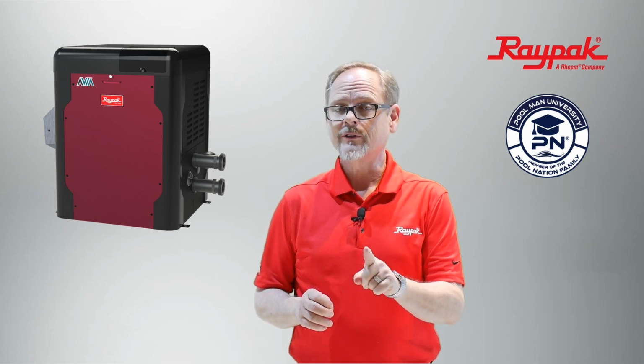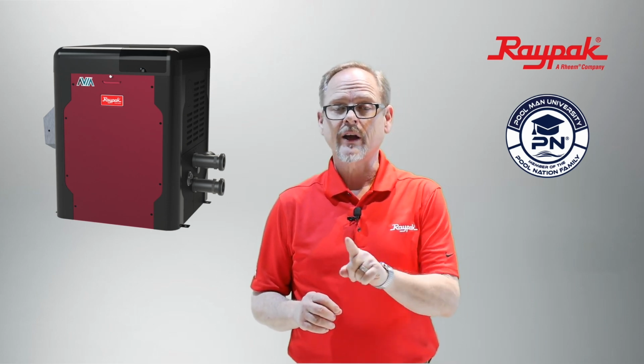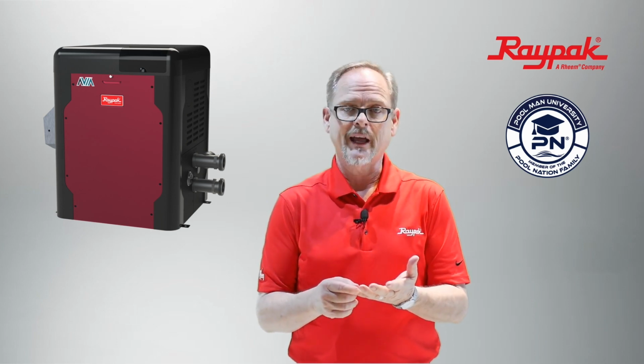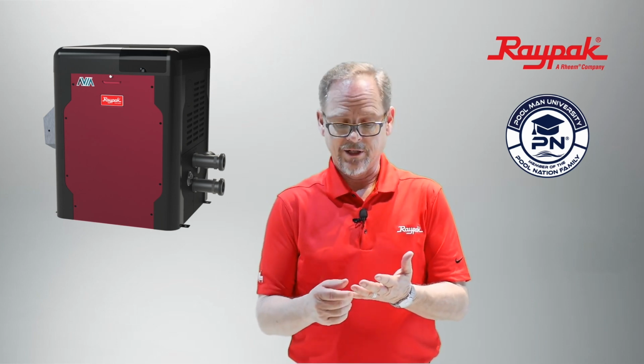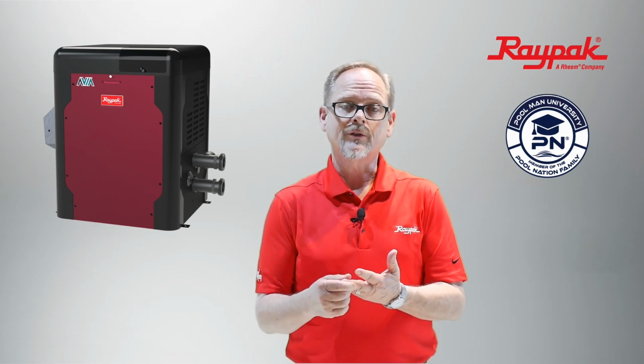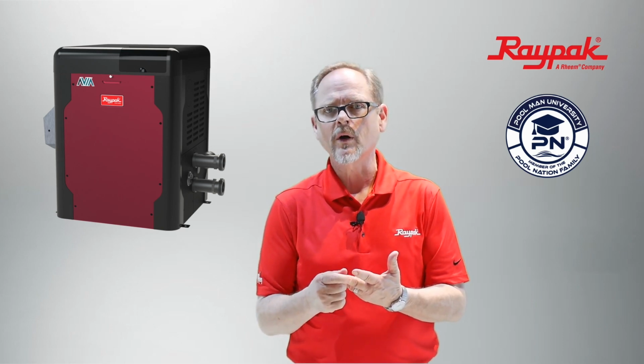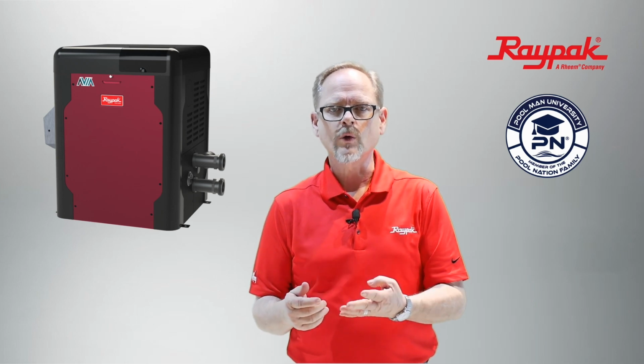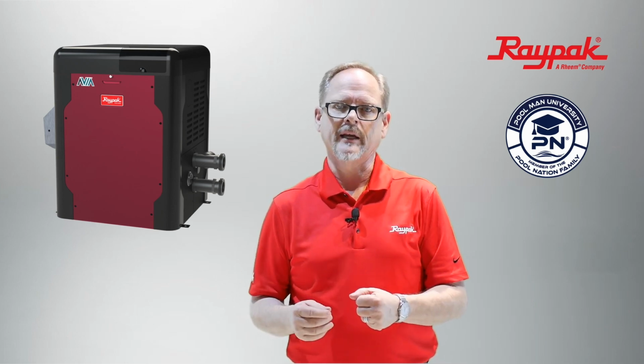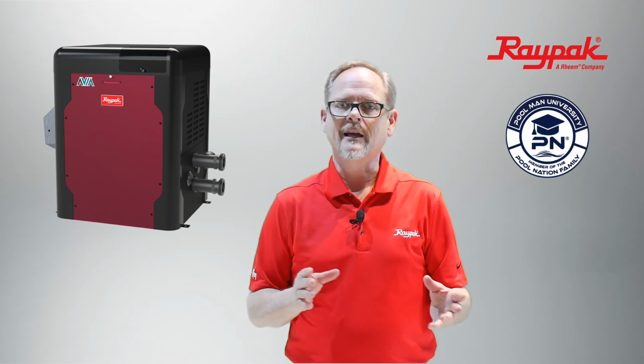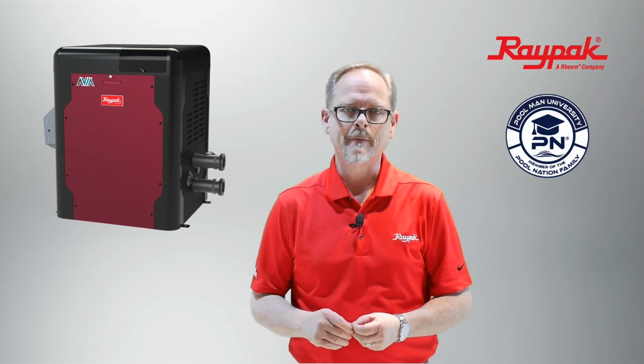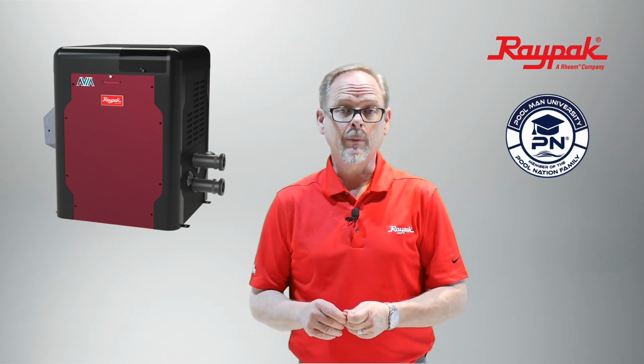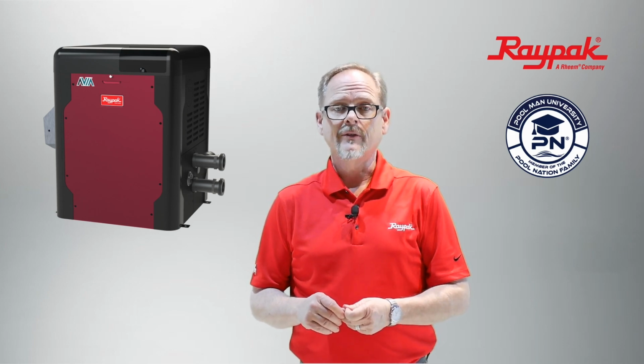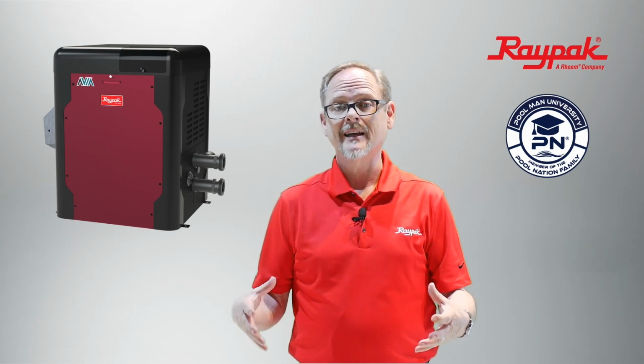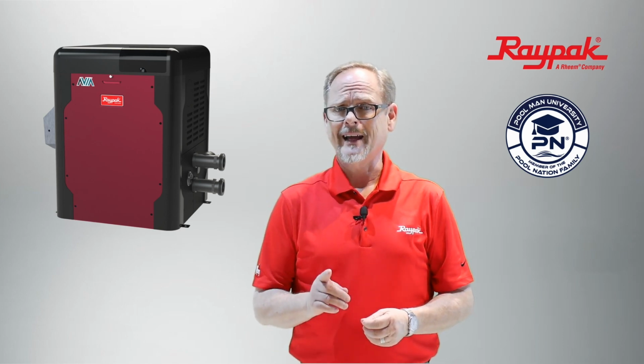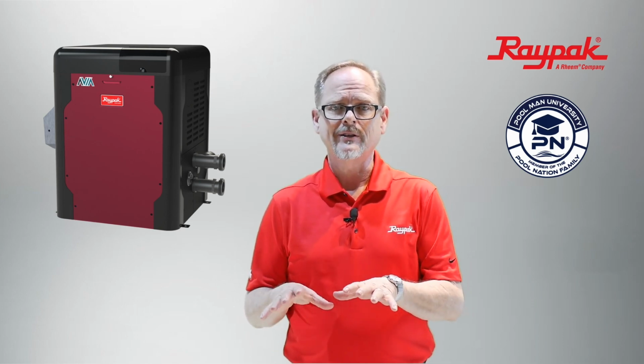Now this differentiates itself from other similar sized products by the fact that it does not have a hot surface igniter. It does not have a pilot assembly. It just has what would be something like a spark plug that fires for 4 seconds and then looks for flame. If it doesn't find the flame, it will start the whole process over again. One other thing that's available as an upgrade is our heavy duty model that contains our NiTek heat exchanger. Now NiTek is what makes it the heavy duty model.